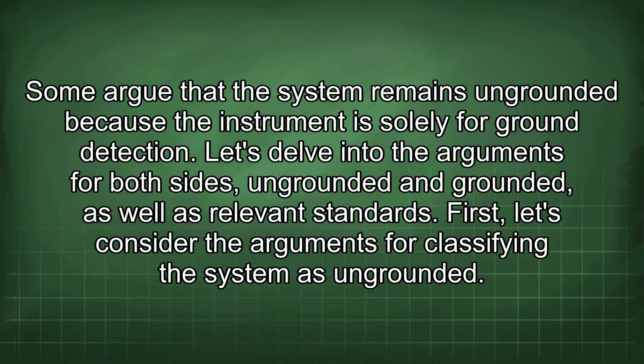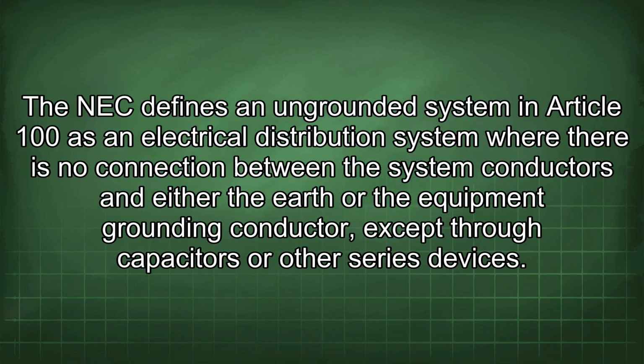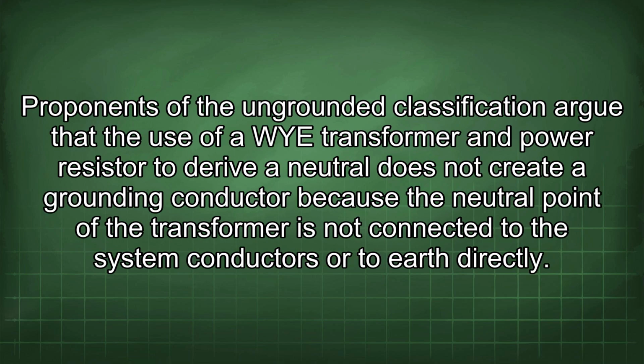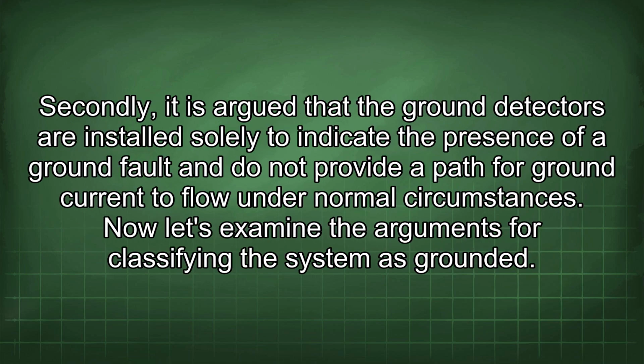First, let's consider the arguments for classifying the system as ungrounded. The NEC defines an ungrounded system in Article 100 as an electrical distribution system where there is no connection between the system conductors and either the earth or the equipment grounding conductor, except through capacitors or other series devices. Proponents of the ungrounded classification argue that the use of a WYE transformer and power resistor to derive a neutral does not create a grounding conductor because the neutral point of the transformer is not connected to the system conductors or to earth directly. Secondly, it is argued that the ground detectors are installed solely to indicate the presence of a ground fault and do not provide a path for ground current to flow under normal circumstances.